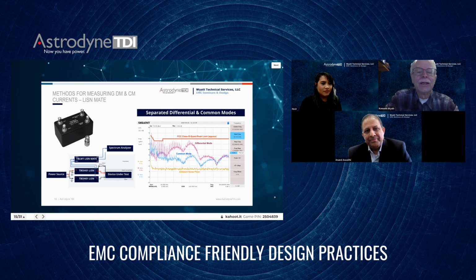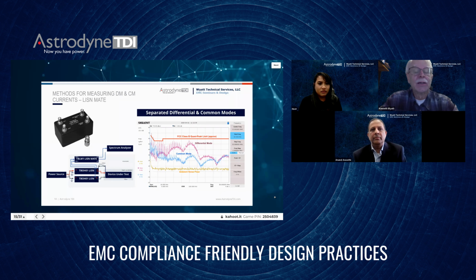One other way to measure or separate out the differential and common mode harmonic noise currents is to use something called a LISN mate. This is marketed by a company called Tekbox, and you use a pair of line impedance stabilization networks, or LISNs, in combination with the LISN mate, which has ports for separating out the common mode and differential mode noise currents.